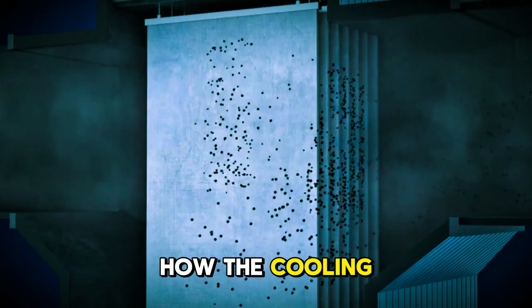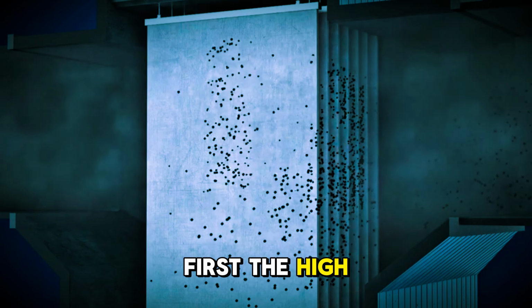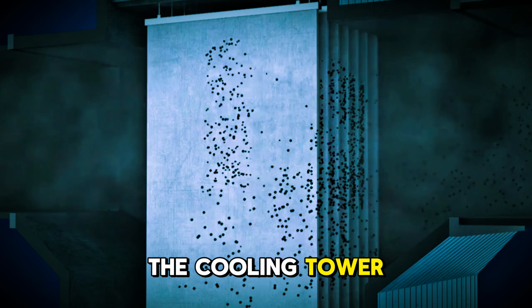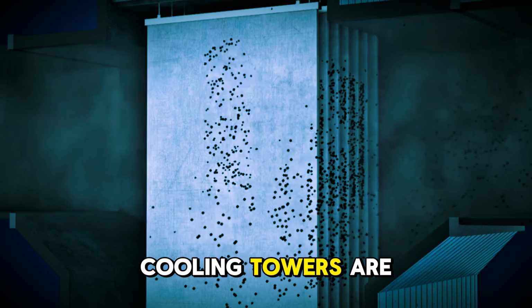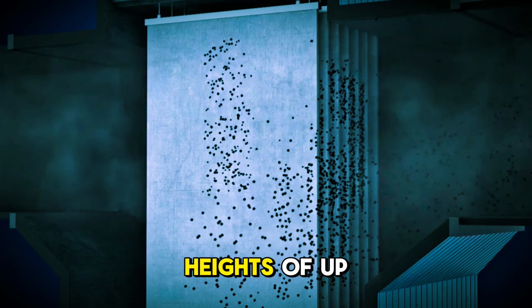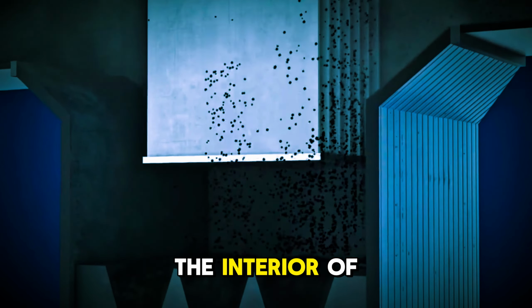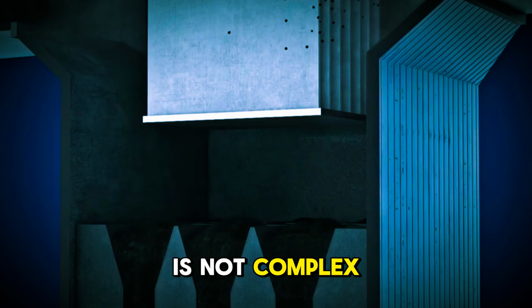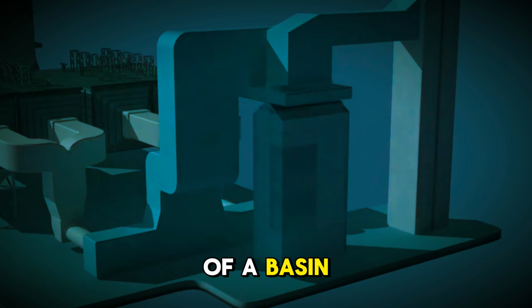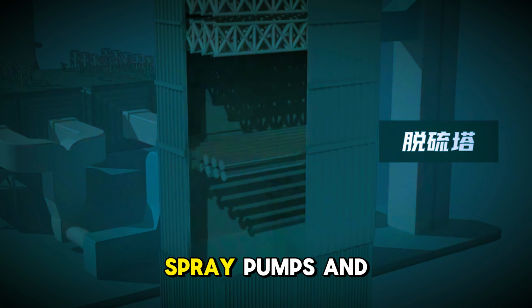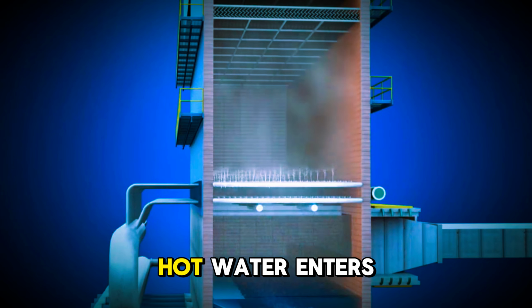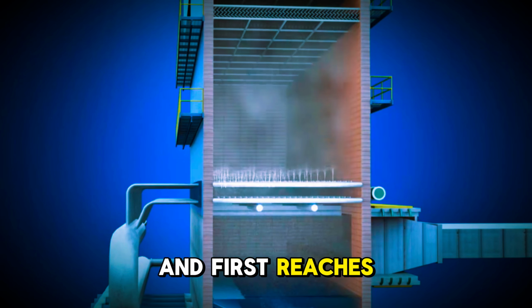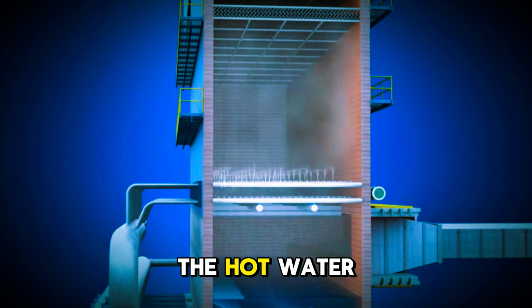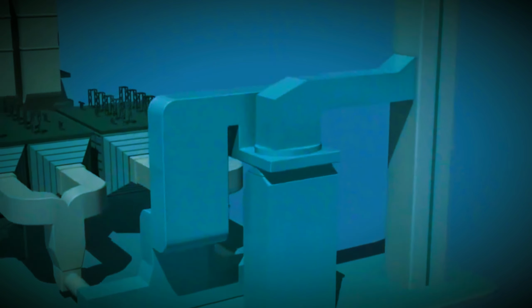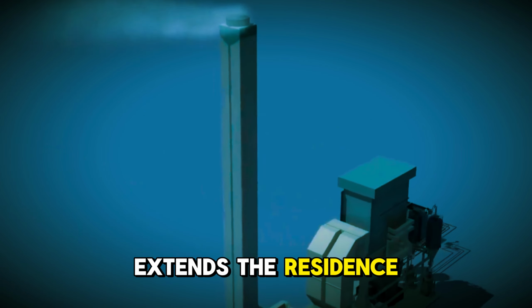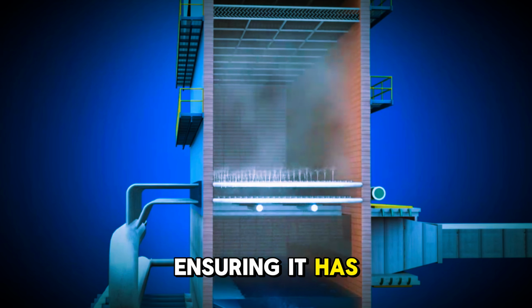Now, let's see how the cooling tower cools this water. First, the high-temperature cooling water enters the cooling tower along hot water pipes. Cooling towers are made of concrete and typically reach heights of up to 200 meters. The interior of a cooling tower is not complex. It primarily consists of a basin, air inlets, heat dissipation fill, spray pumps, and a water reservoir. Hot water enters through the inlet and first reaches the spray pumps. Afterward, the hot water flows to the heat dissipation fill.